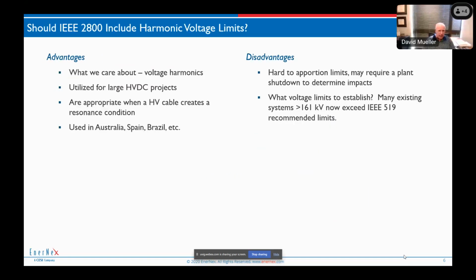Well, before I do that, let me say that we had a lot of discussion. Should we be limiting harmonic voltage or harmonic current? Harmonic voltage is what we care about. It's what we want to limit on the system. It's the power quality metric that's important. And it's used for larger projects where there's a lot of engineering work that can be done and a lot of large system studies that can be done. And it's used around the world.